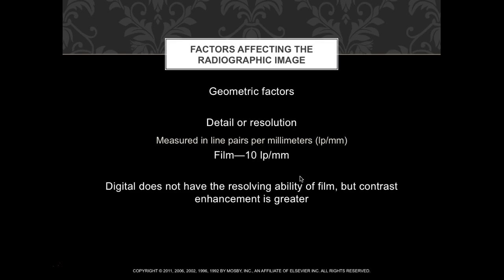For geometric factors and detail or resolution, we measure in line pairs per millimeter (lp/mm). Film achieves about 10 line pairs per millimeter. Digital does not have the same resolving ability as film, but contrast enhancement is greater and it's enough to make it worthwhile.